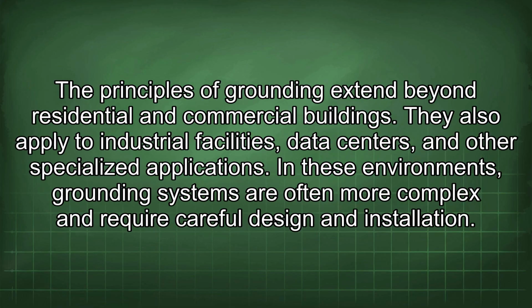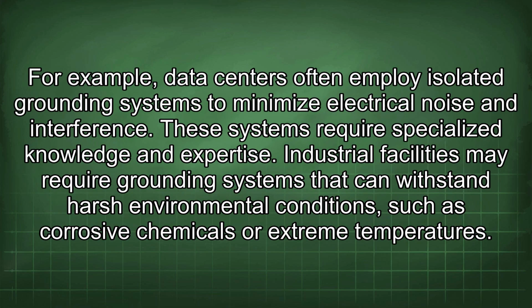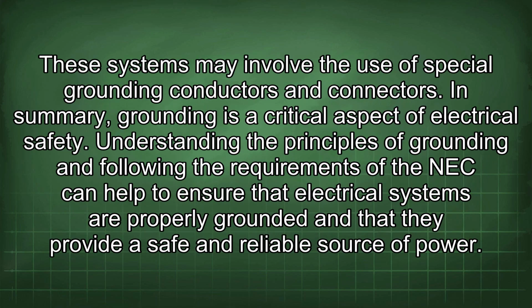Principles of grounding extend beyond residential and commercial buildings. They also apply to industrial facilities, data centers, and other specialized applications. In these environments, grounding systems are often more complex and require careful design and installation. For example, data centers often employ isolated grounding systems to minimize electrical noise and interference. These systems require specialized knowledge and expertise. Industrial facilities may require grounding systems that can withstand harsh environmental conditions, such as corrosive chemicals or extreme temperatures. These systems may involve the use of special grounding conductors and connectors.